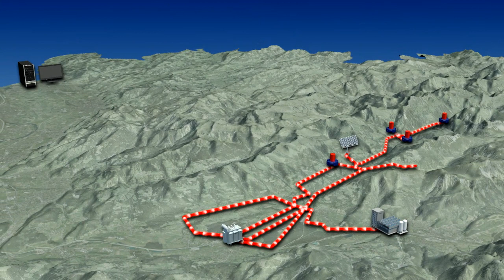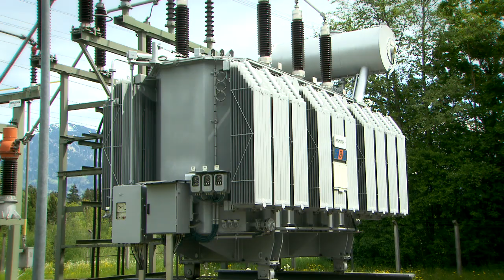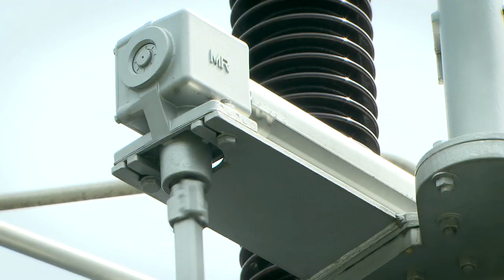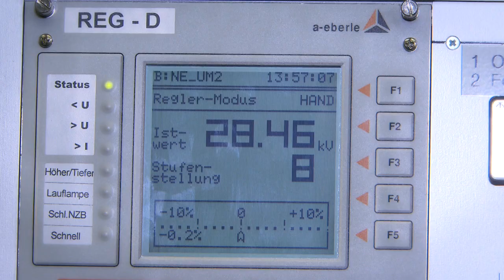The CVCU evaluates that information and communicates an optimized set value to the main transformer substation in Nenzing, the gateway to the Biosphere Reserve. Its regulating transformers are controlled in a way that ensures limits of operating voltage are never exceeded in any part of the system.